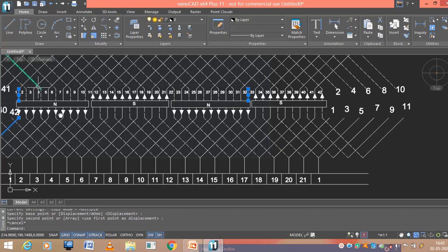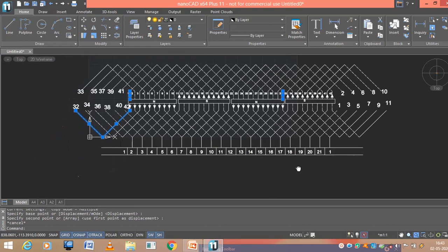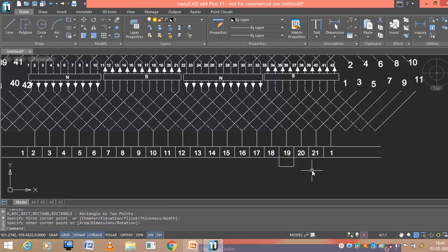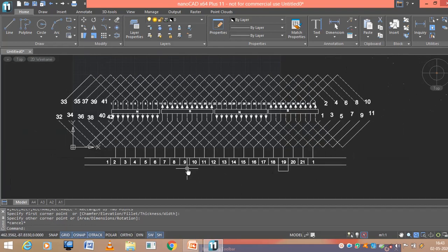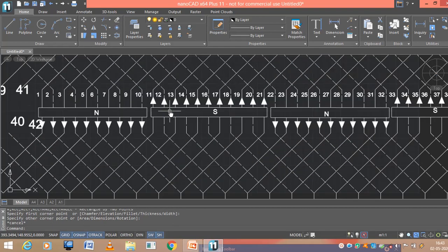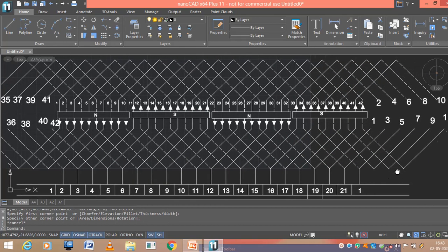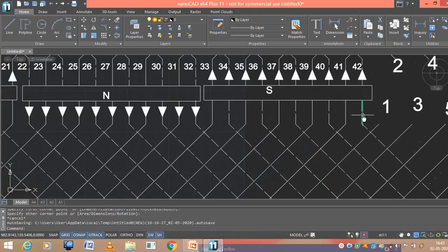It means 32 and then 1 is the location, right? 32 and 1. So here I have considered this 1. If you want, where is 32? A brush, and both the conductors are under the influence of north pole. That's why this is your positive brush. Now I need one more brush, that should be a negative brush. So for that, the conductor should be under the south pole. For example, let us go for this, 42 conductor is under the south pole.